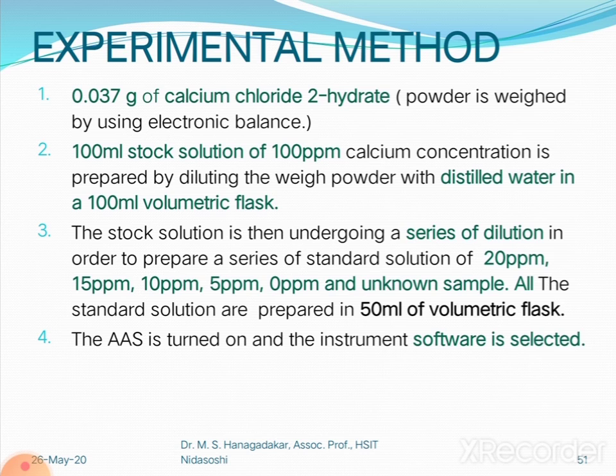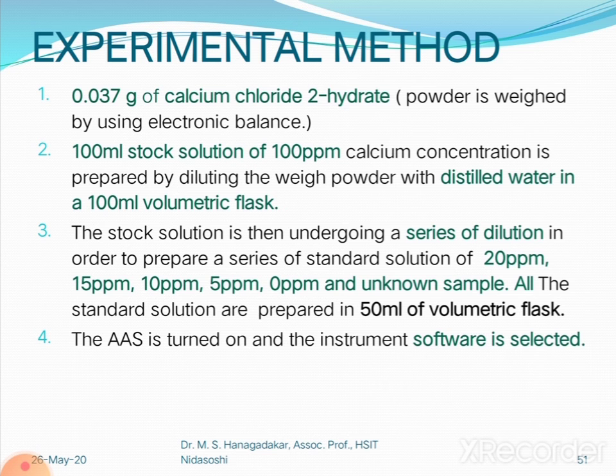All standard solutions of 20 ppm, 15 ppm, 10 ppm, 5 ppm, and 0 ppm are prepared in 50 ml volumetric flasks by taking known volumes of the 100 ppm stock solution. Step four: the atomic absorption spectrophotometer is turned on and the appropriate software is selected, since the instrument is software-operated.